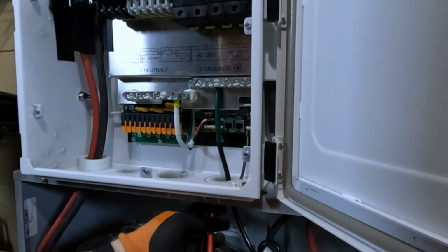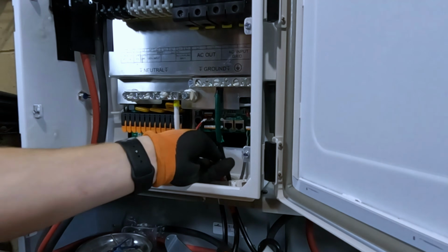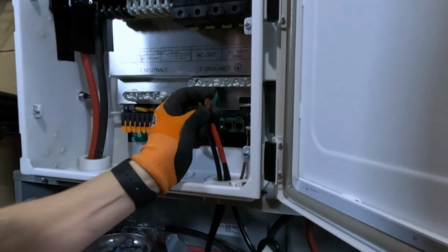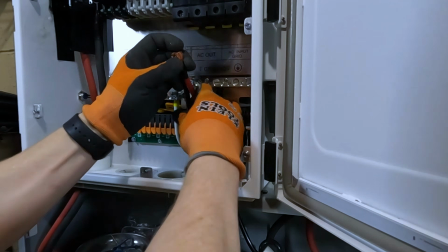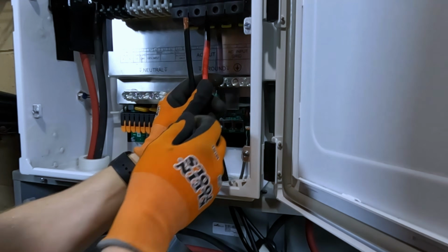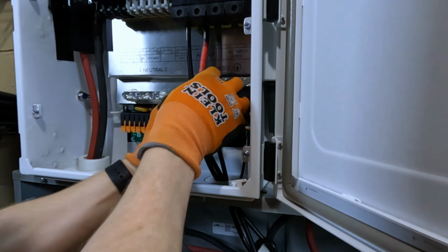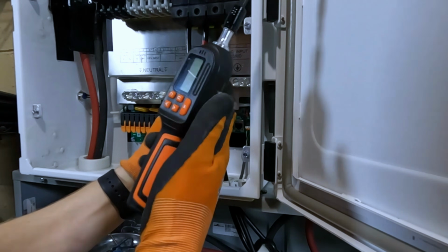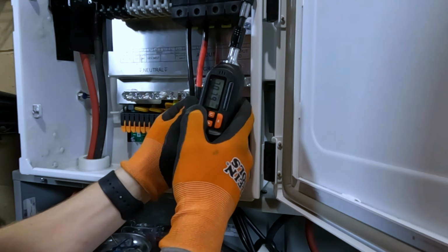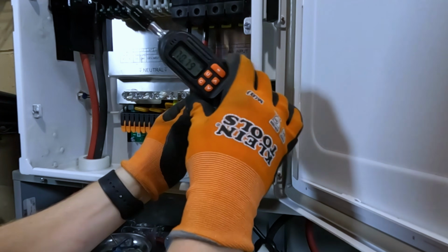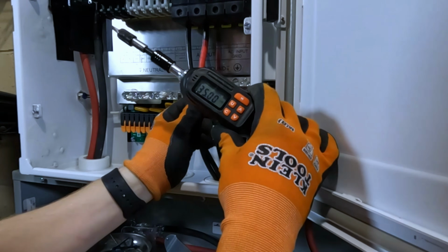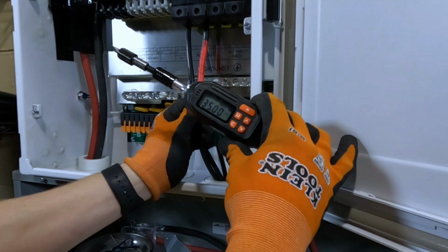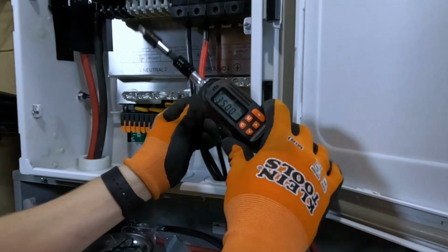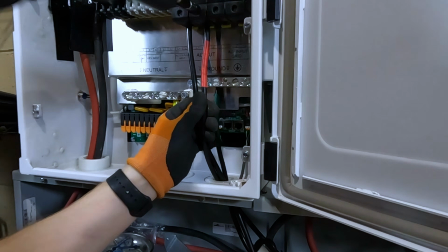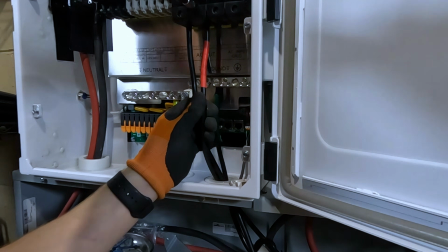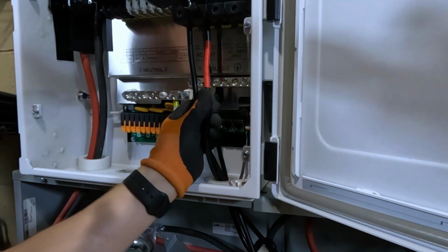So we'll feed these lines up from underneath. I do already have both sides taped with the L2 red tape. And we'll slide them up into the output terminals. I'm going to use my VVOR torque wrench, which should already be programmed to the torque spec for these breakers, which is 35 inch-pounds. Hopefully that's actually showing up. So I'm going to hold the one in there and just torque it down.